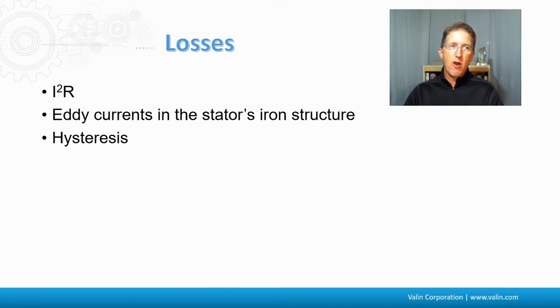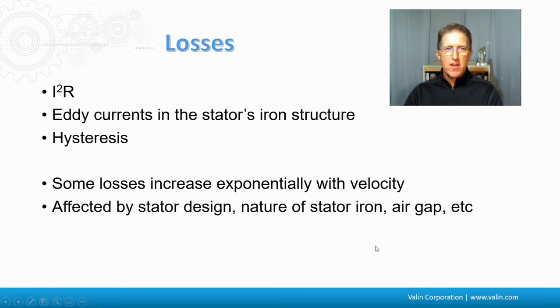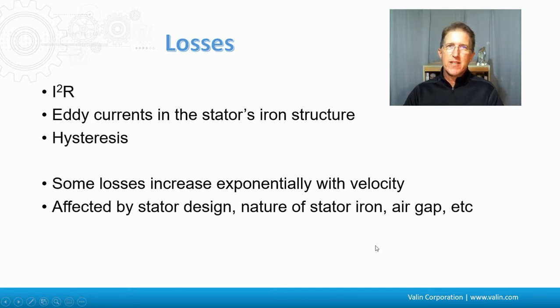There are I-squared-R losses, eddy currents in the stator's iron structure, and hysteresis. Some of those losses increase exponentially with motor velocity. Others are affected by the stator design, the nature of the stator iron, the air gap, etc. That's why you get variations in motor designs and how well they perform.